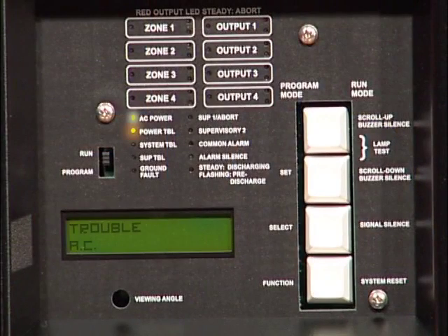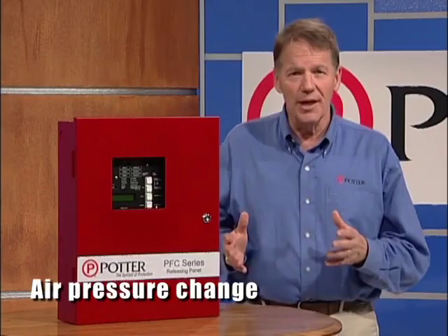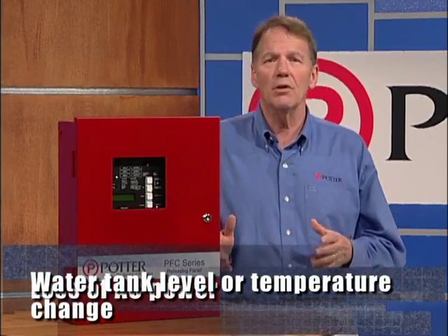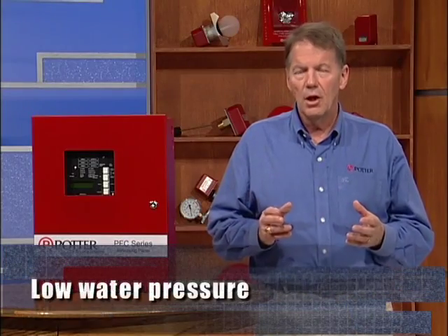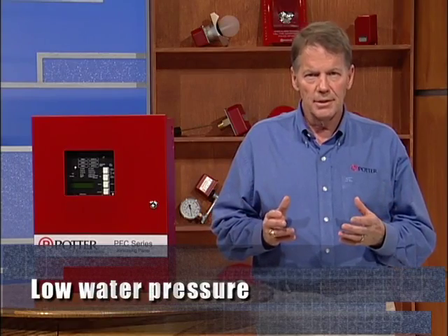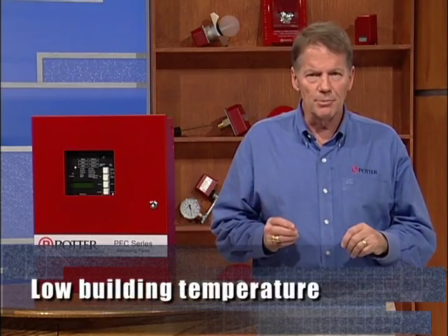For example, a supervisory signal may be triggered because a valve is closed, an air pressure change is detected, a water tank level or temperature change, low water pressure is detected, or a low building temperature is detected.